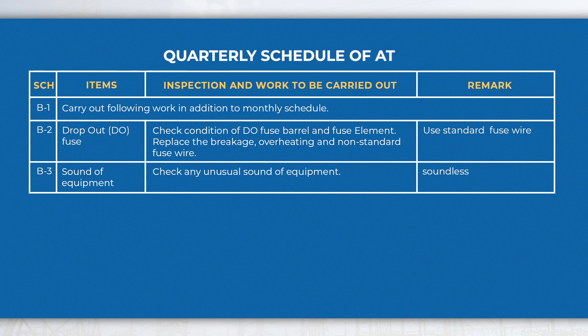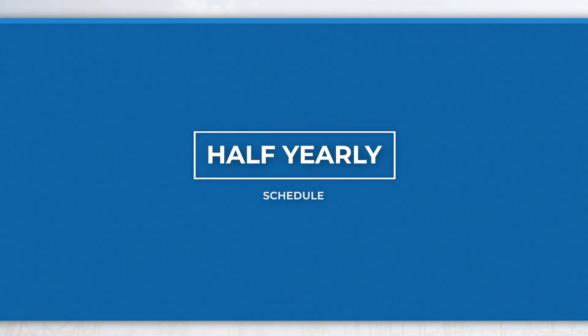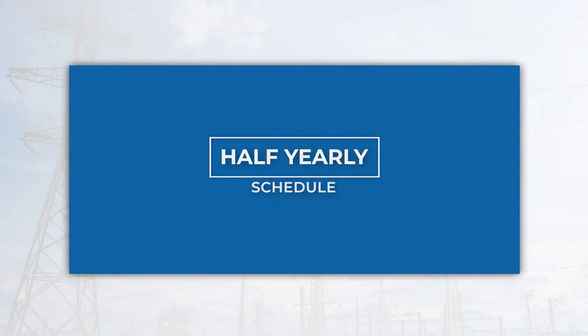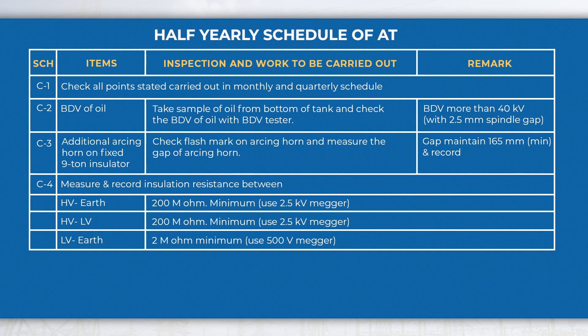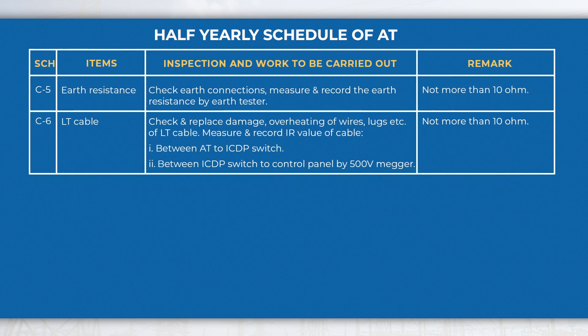In the half-yearly schedule, perform activities like measuring the insulation resistance value and checking the BDV of oil, etc., in addition to monthly and quarterly schedule activities.